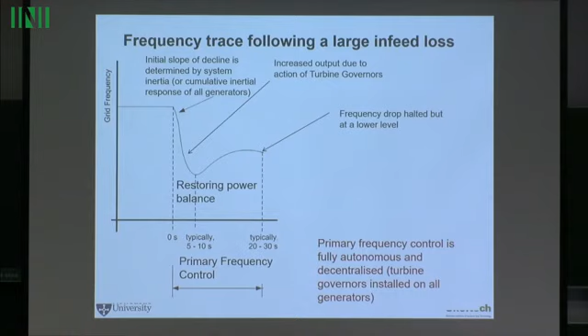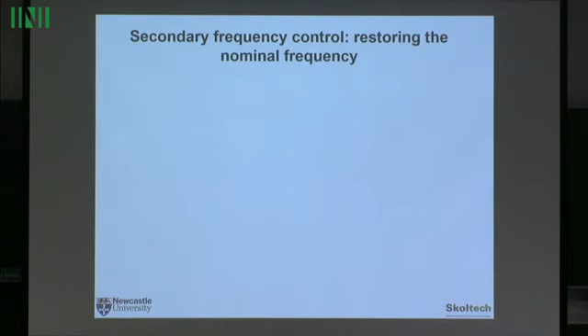Coming back to frequency control: at the end of primary frequency control, power balance has been restored, but the frequency is less than 50 Hertz, because the controllers are proportional controllers and so have a steady state error. This triggers secondary frequency control, which restores nominal frequency - effectively connecting more generation to bring frequency back up to 50 Hertz. But it's different, because secondary frequency control is centrally controlled, whereas primary is autonomous and decentralized - the system operator doesn't even know what's happening during primary control.